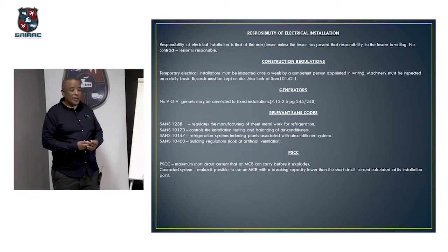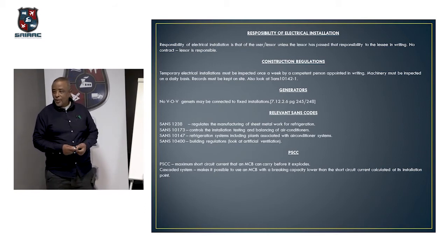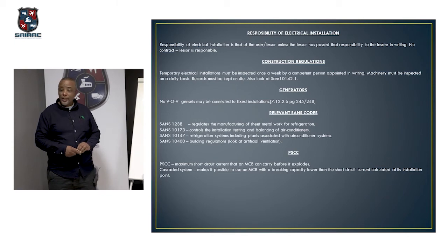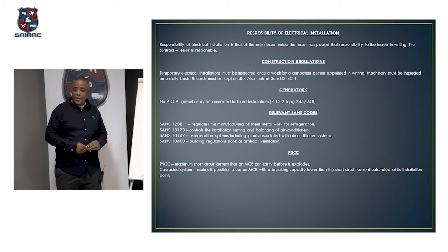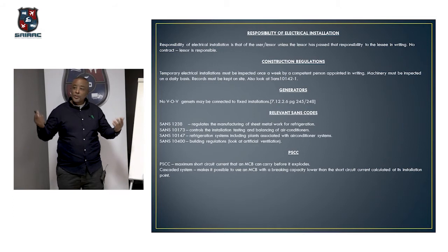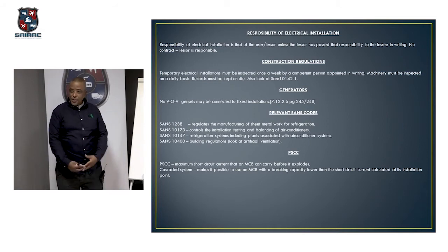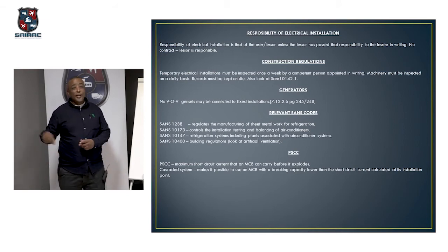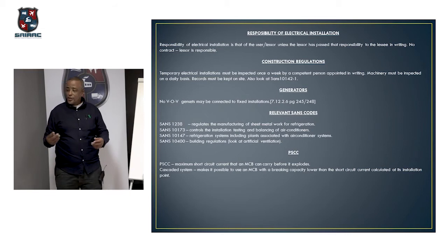PSCC, it's the maximum short circuit current that a circuit breaker can carry before it explodes. PSCC is very important, especially in hazardous areas where there's explosions. I've seen a video, I think it was from CBI. The guys had their switching suits on, they looked like spacemen, and when they went to do switching, downstream there was a fault. Even with their switching suits, both of them died and got burnt. So PSCC is very important.